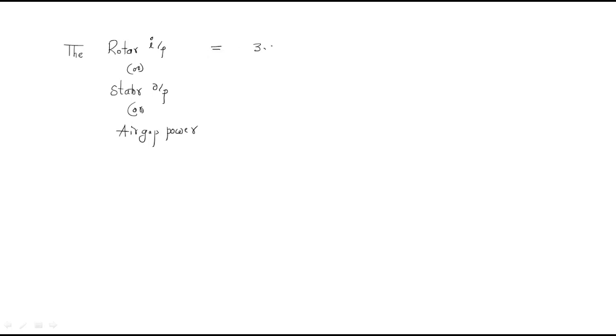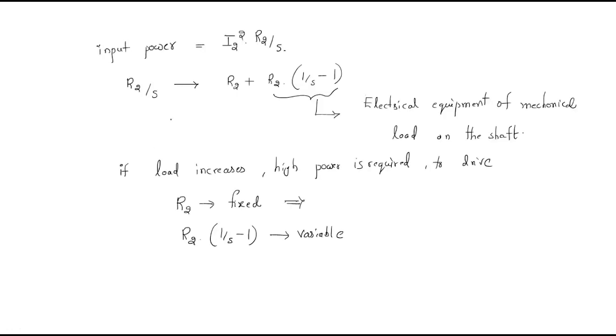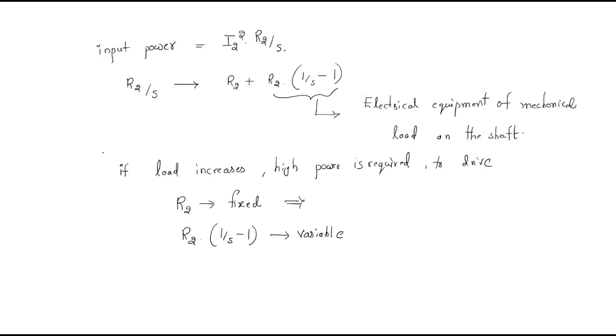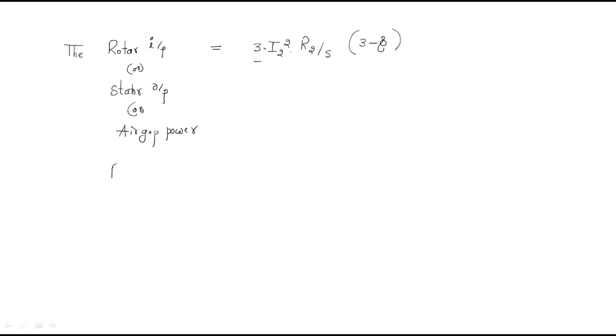The air gap power is given as: Air gap power = 3 × I2² × (R2/s) — the factor 3 is for the three-phase system. This input power to the rotor is converted into two things: one is the loss power and the other is the output power. The rotor loss is: 3 × I2² × R2, which is the fixed value representing rotor copper loss.